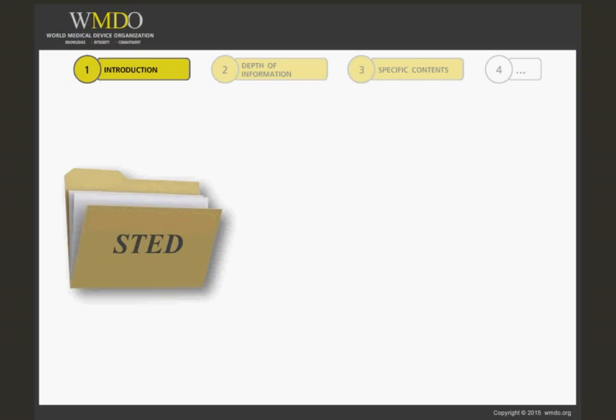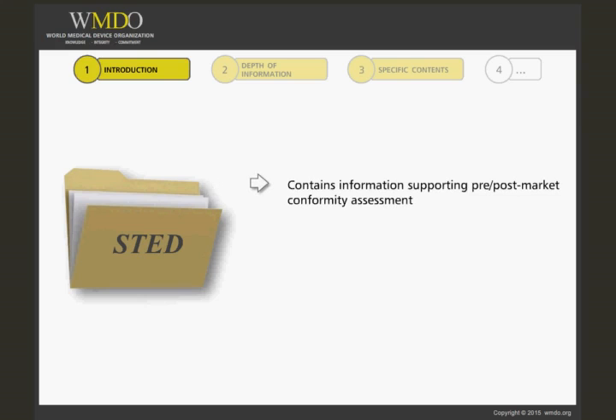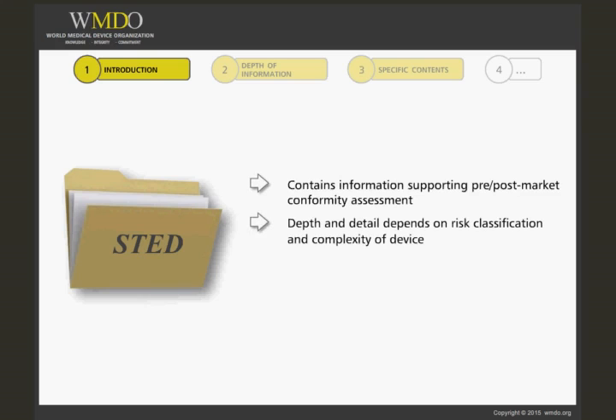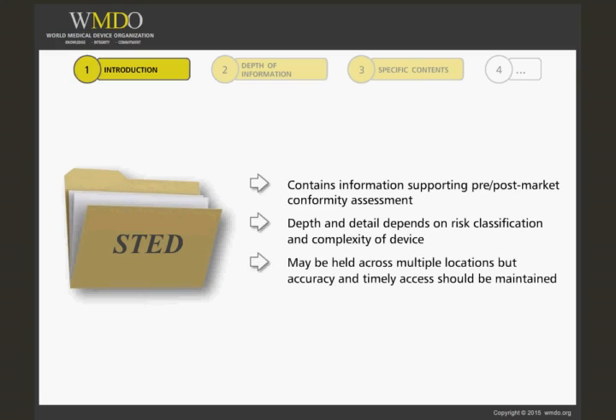The STED contains information supporting pre- and post-market conformity assessment activities. Its depth and the details included depend on the risk classification and complexity of the device. The technical documentation may be held across multiple locations, but manufacturers should maintain accuracy of individual components and ensure timely access to STED contents in response to regulatory requests.